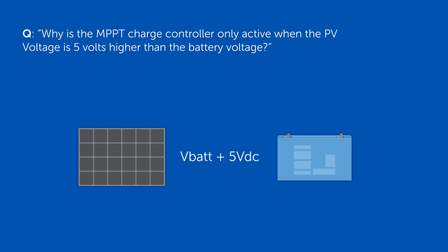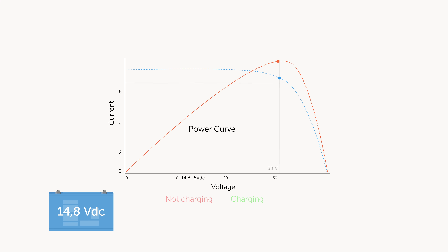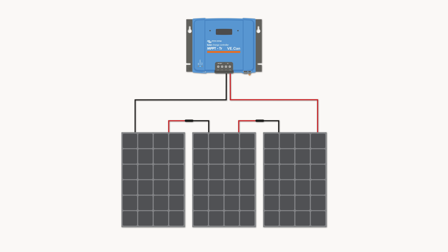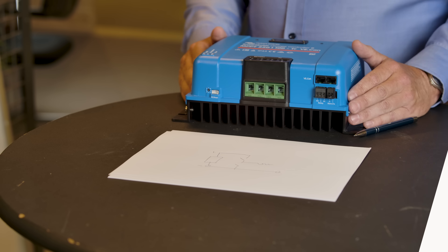Sometimes you get a question: why is the MPPT charge controller only active when the PV voltage is 5 volts higher than the battery voltage? Well that has a reason. Because the PV voltage of a panel will lower as soon as you start loading it. So if you start the MPPT charge controller too soon, it takes energy to run but it's not able to take energy from your solar panel — effectively you will drain your batteries. So the MPPT charge controller will only be active if it sees a PV voltage high enough that it can charge the batteries without draining them. This also means the higher the PV voltage, the sooner the MPPT charge controller will start working. If you have more panels in series and start off with a higher voltage, the sooner the charge controller will be able to charge your batteries, and the longer it will last during the day.